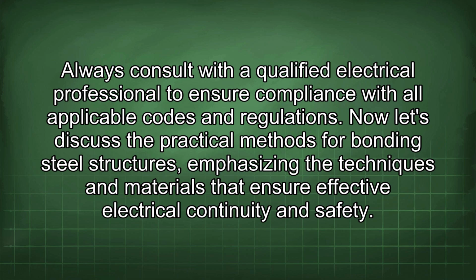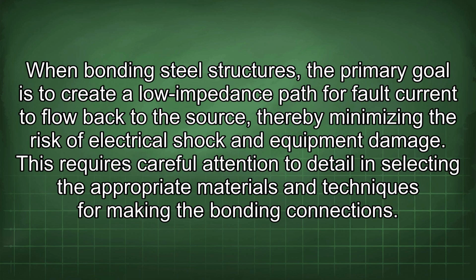Now let's discuss the practical methods for bonding steel structures, emphasizing the techniques and materials that ensure effective electrical continuity and safety. When bonding steel structures, the primary goal is to create a low impedance path for fault current to flow back to the source, thereby minimizing the risk of electrical shock and equipment damage. This requires careful attention to detail in selecting the appropriate materials and techniques for making the bonding connections.